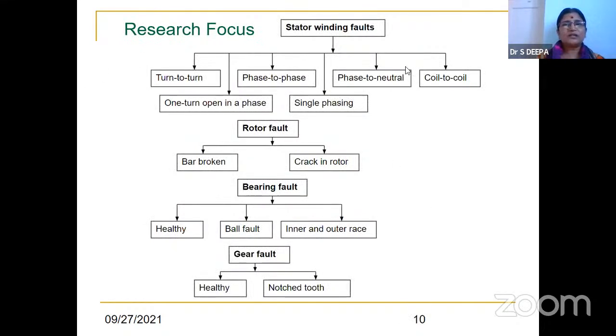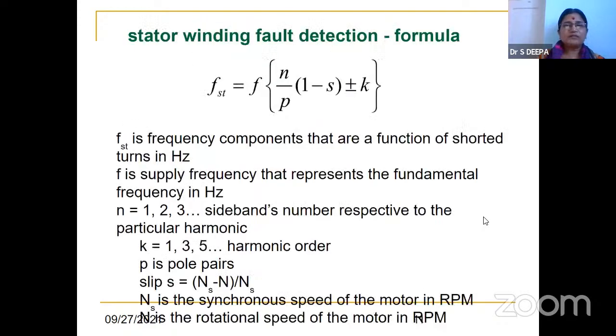Next, the types of fault that I focus on here. We have the stator winding fault. In the stator winding fault, we can consider turn-to-turn fault. You would have seen the motor, the coil and all. So there is a single turn-to-turn, one turn open in a phase, phase to phase, single phasing, phase to neutral, and coil to coil. So there are different types of fault in the stator winding. Then rotor fault, rotor bar broken, crack in the rotor. Rotor fault is a very rare fault. And bearing fault is the dominant fault in machines: healthy, ball fault, and inner and outer race. Gear fault: healthy and notch tooth. All these types of fault we simulated.